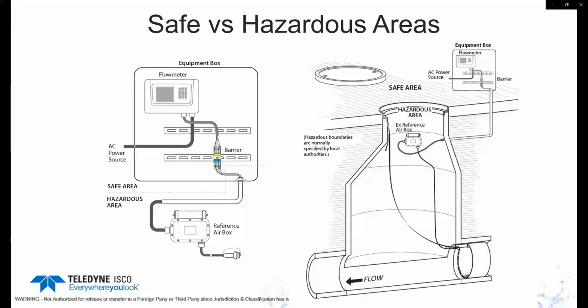There are different things you have to follow when setting up an intrinsically safe application. The safe environment, outside the manhole, is where you'd have your equipment, whatever flow meter you're using, and you'll always have some sort of barrier with this design.